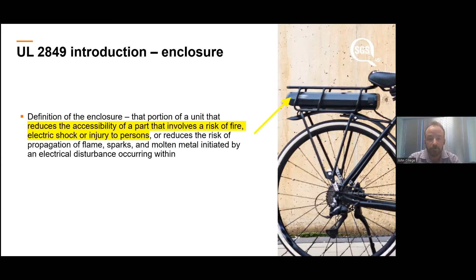And so enclosures can be polymeric. If it's a plastic polymeric enclosure, it has to have a minimum rating of V1, and that's per UL 94. So the enclosure would be a minimum of V1. Internal components would be a minimum of V2, and an RTI of no less than 80 degrees C, and have UV resistance. So typically the polymeric material would have been tested for UV resistance, or we can also test that material. Metallic enclosures need to be corrosion resistant, and we'll look to guidance in UL 50E for enclosure testing as well.